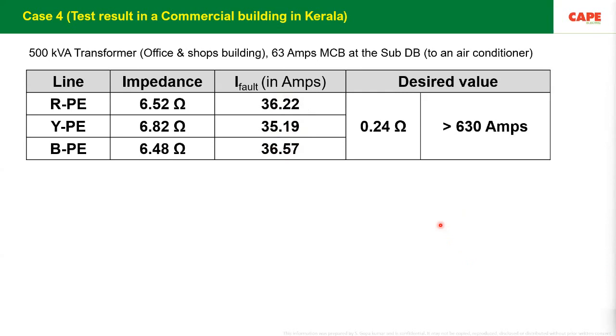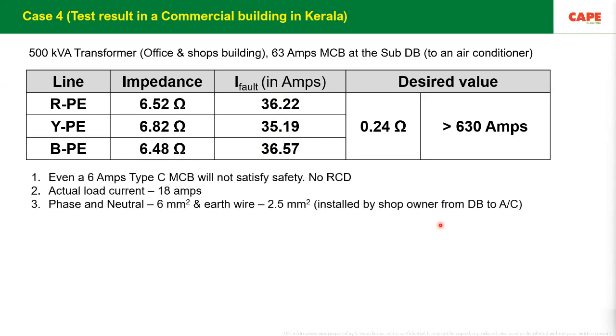As a result, if this air conditioner develops a fault, you can be sure that the result is fire or an accident. The result of this particular study is that even if he had a 6 amps type C MCB, even a 6 amps MCB cannot trip in this situation. So the installation was so bad. The actual load current was 18 amps, and for the phase and neutral he has used 6 square mm, and for the earth wire he has used a 2.5 square mm wire.